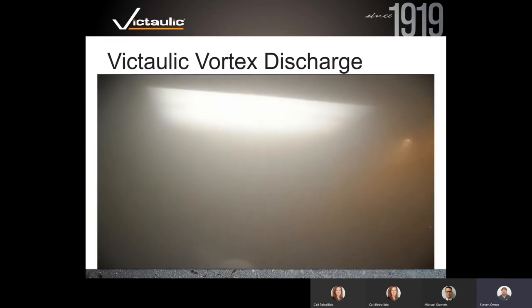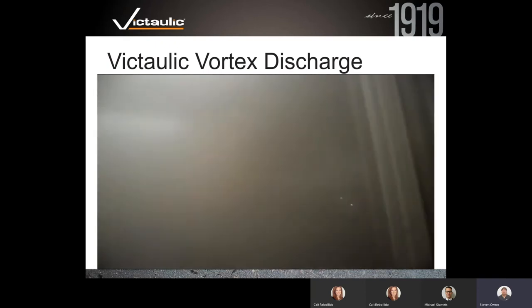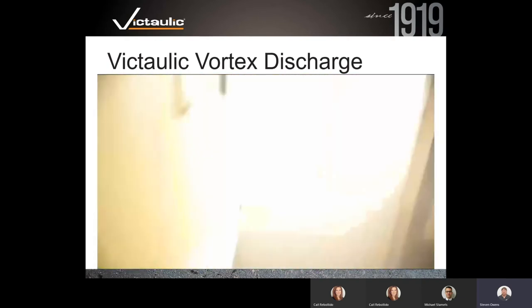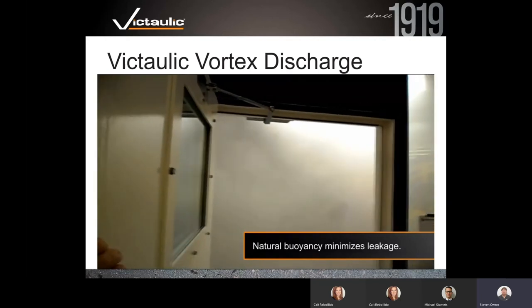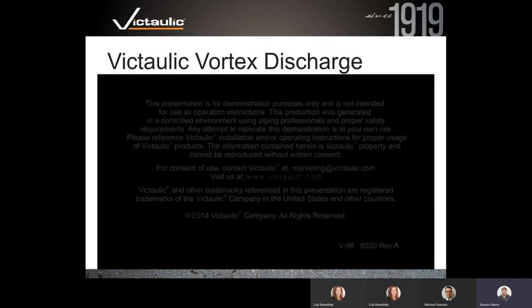You can see a gentleman has tried to light his lighter inside the room and cannot do so. The room is fully filling up. This is a 3D extinguishment system, so fires underneath or inside of cabinets will be extinguished as well as surface fires. He's now just stepped out. We've been doing this discharge with the room open, and because of that neutral buoyancy — 78% of what's in that room is already nitrogen — the dynamics of the emitter flow keep pulling the mist right back into the room, demonstrating the minimal room integrity requirement.